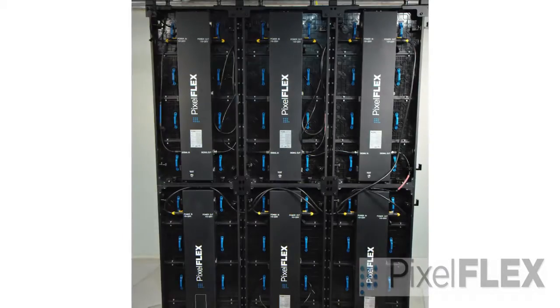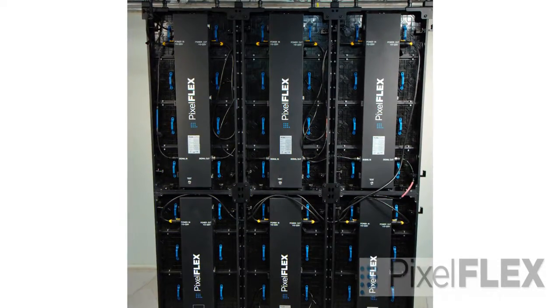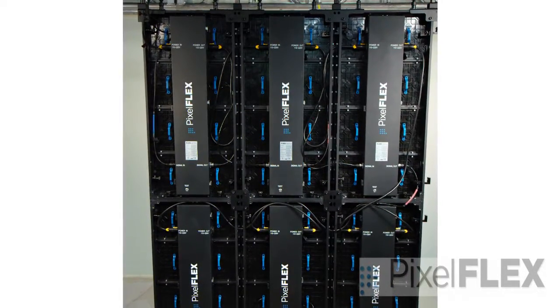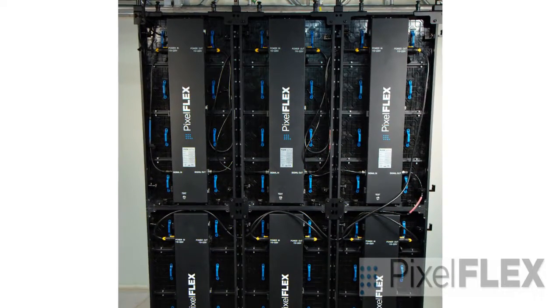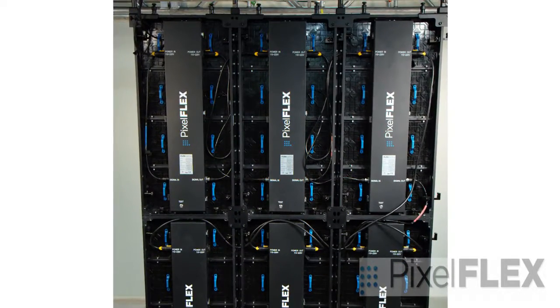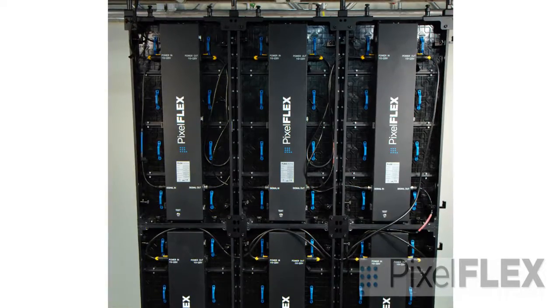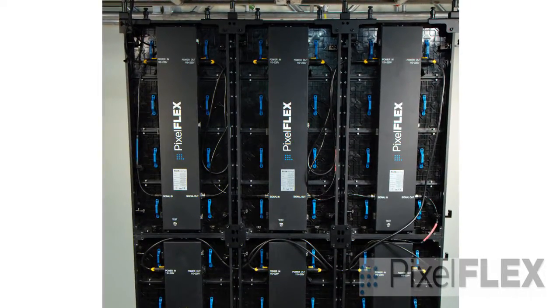FLEXLite Plus cabinet power is daisy-chained. To determine how many cabinets can be on one circuit, we need to first know what the circuit specifications are, as well as the total power requirements of your array. We also need to follow some basic electrical laws and practical common practices.